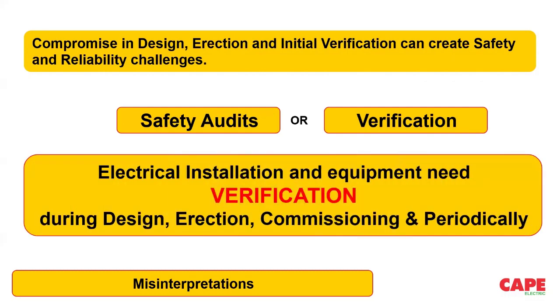So safety verification is the correct word. Electrical equipment and the installation need a verification during its design, erection, commissioning, and periodically. It's very much important. Not only during the product testing, verification is required during design of the electrical installation, erection of the installation, commissioning of the installation, and periodically you should do verification.